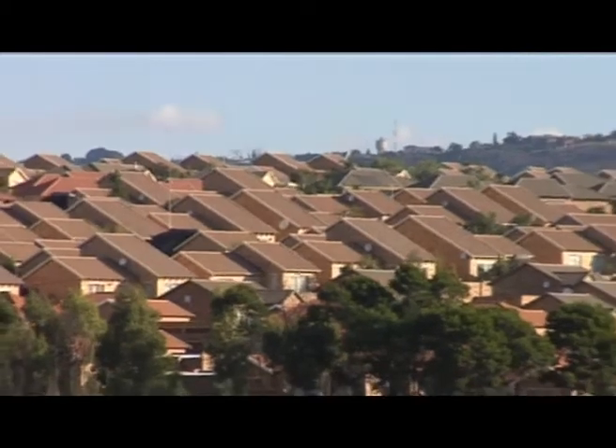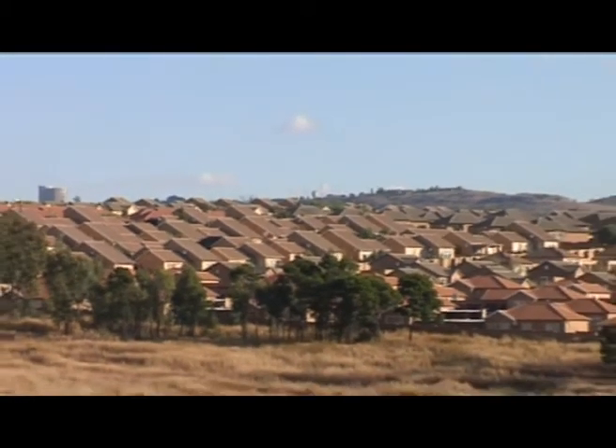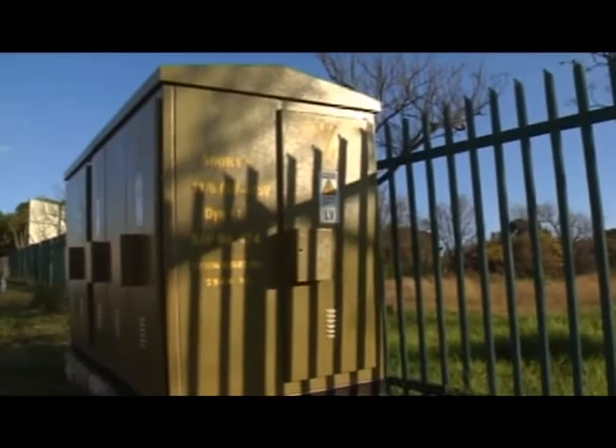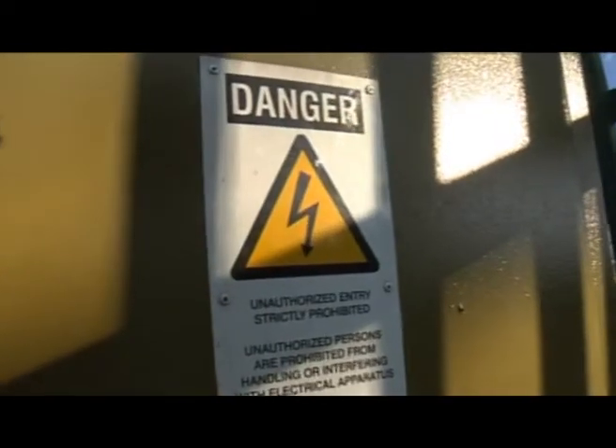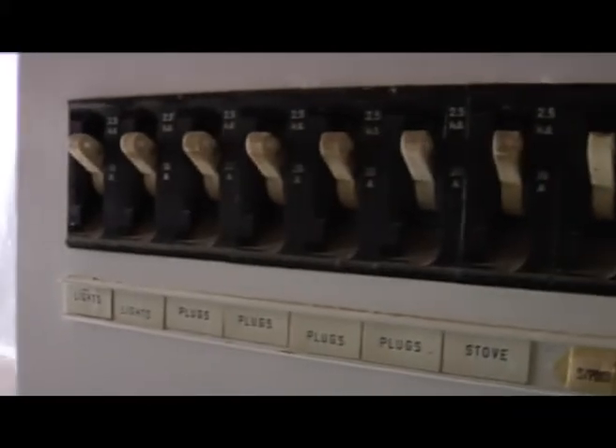This is a very important factor, because the moment you shed a domestic area, three to four hours later the twenty or thirty percent of geysers that were actually on before the load shed occurred — 100 percent of those geysers will now be on. So you've probably got a load three, four, up to five times higher than what you shed into. The implication on switchgear and cabling is horrendous.